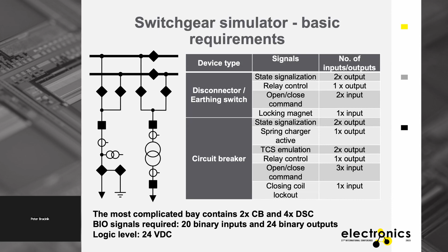20 binary inputs and 24 binary outputs must be simulated. The logic level for these inputs were taken as 24 volts DC for 2 reasons: the first is safety, since students will be dealing with this in the lab, and the second is that this is the normal voltage used very often in power substations for such circuitry. So the students or practitioners will face a real situation like in real power substations.